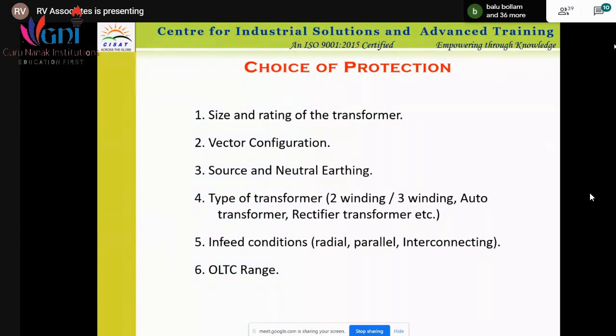The rating of an earth transformer is almost around 5% of the rating of the transformer. Then there are other conditions for protection, like parallel connections, interconnections, and zigzag connections. That is called interconnection. Then OLTC range depends on what the range of the OLTC is. Normally, these days, because of power electronics equipment, we are using OLTC. But still, in some earlier transformers, we have offload tap changers, though very rarely used.